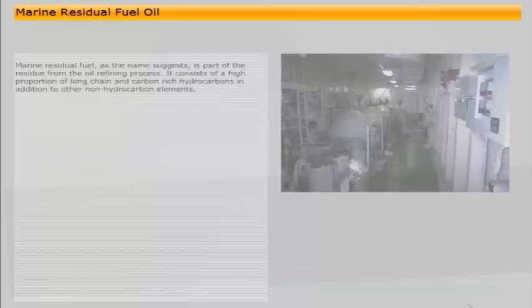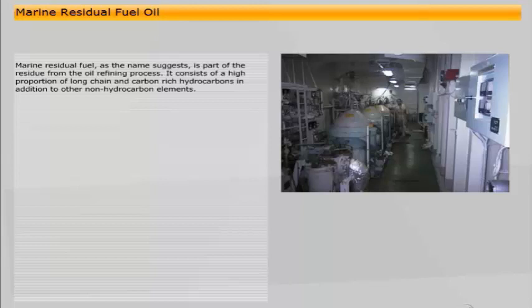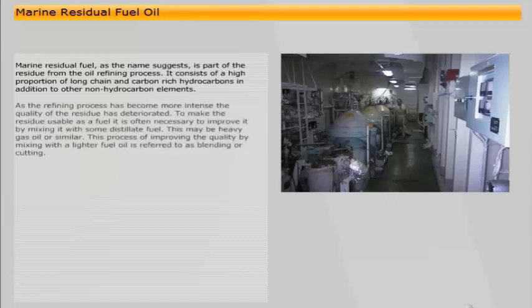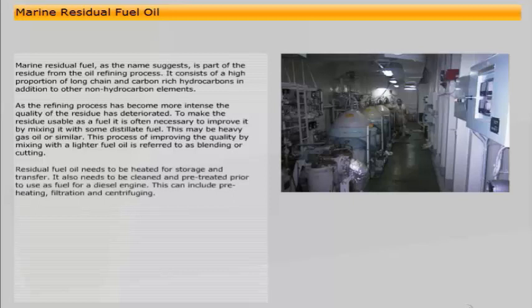Marine residual fuel, as the name suggests, is part of the residue from the oil refining process. It consists of a high proportion of long chain and carbon-rich hydrocarbons in addition to other non-hydrocarbon elements. As the refining process has become more intense, the quality of the residue has deteriorated. To make the residue usable as a fuel, it is often necessary to improve it by mixing it with some distillate fuel, such as heavy gas oil. This process of improving the quality by mixing with a lighter fuel oil is referred to as blending or cutting. Residual fuel oil needs to be heated for storage and transfer, and also needs to be cleaned and pretreated prior to use, including preheating, filtration and centrifuging.